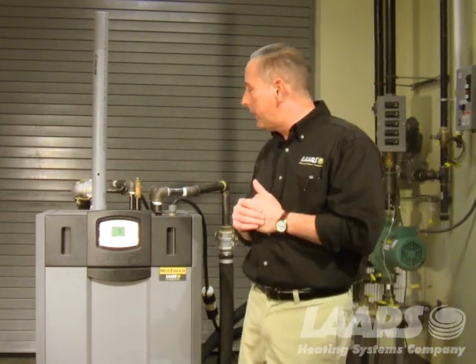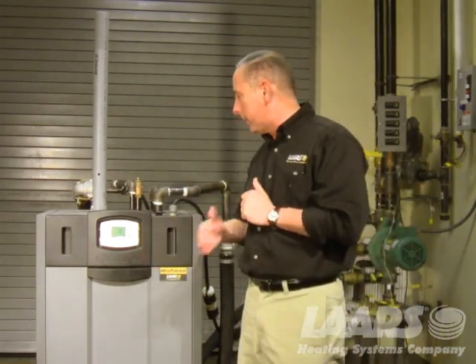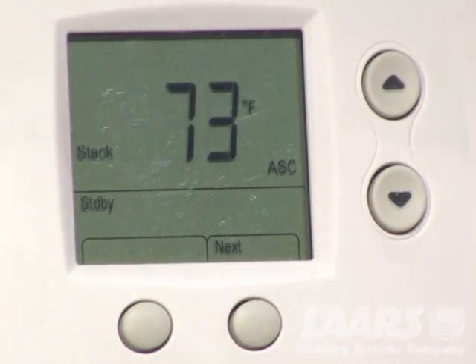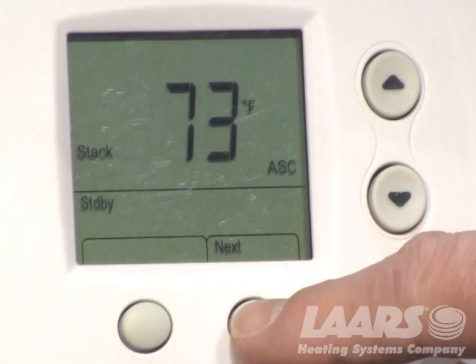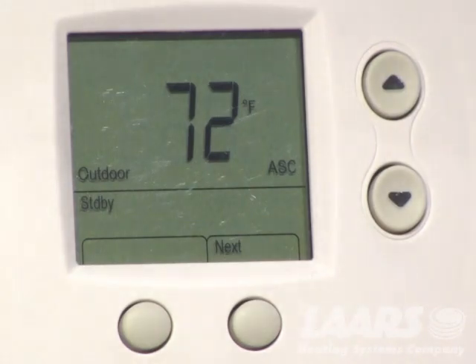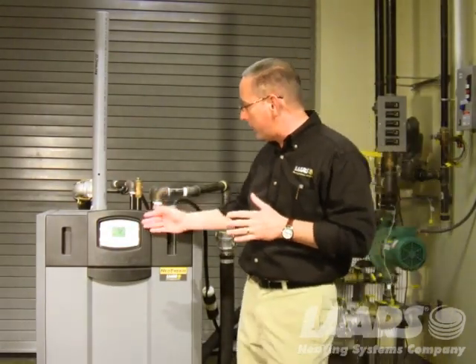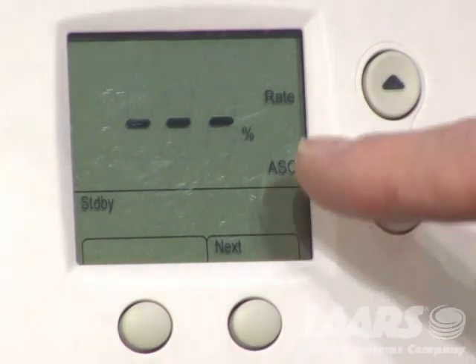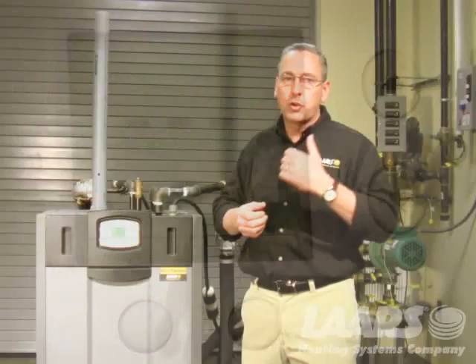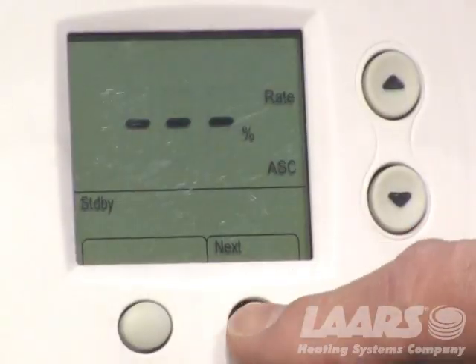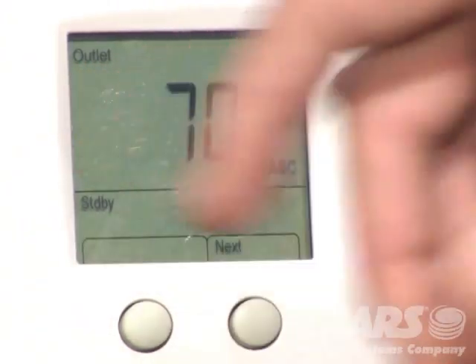There are three modes of operation: user mode, setup mode, and diagnostic mode. In user mode, simply press the next button to scroll through. It shows outlet temperature; press next for inlet; next again is delta T; next again is domestic hot water, which we just set up. Next again is stack temperature — if the boiler was running it will show the stack temperature. Next is outdoor temperature; when using outdoor reset you must use the outdoor sensor, registering 72 today. Next again shows the rate of fire — is it running at 20% or 100%? I'll scroll back to the outlet screen.